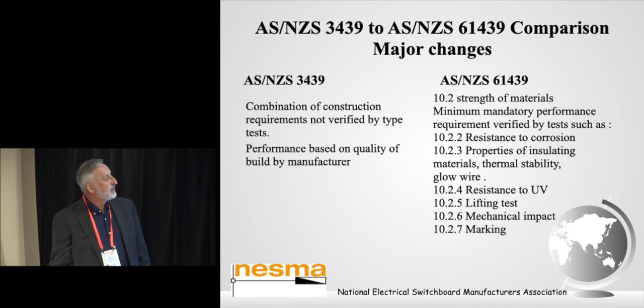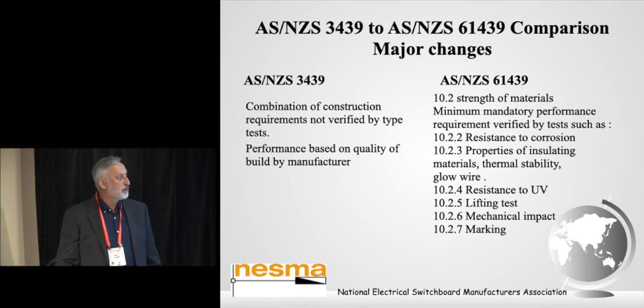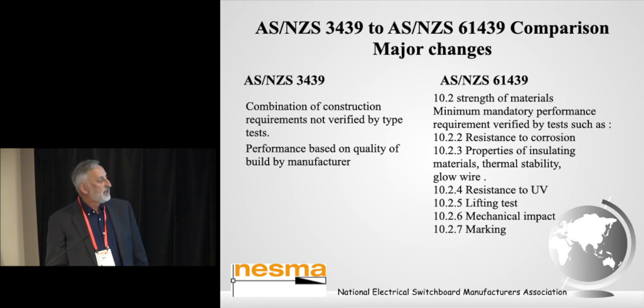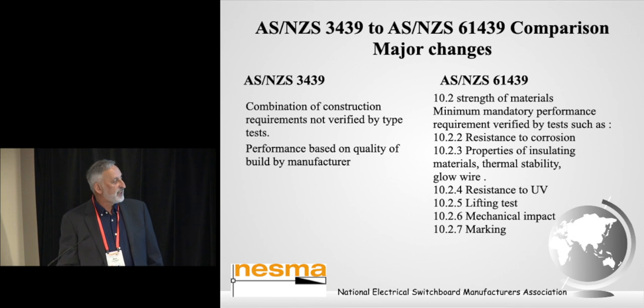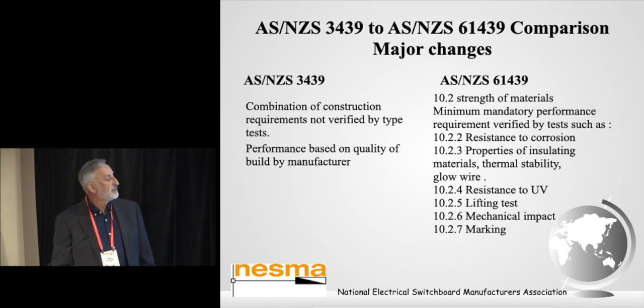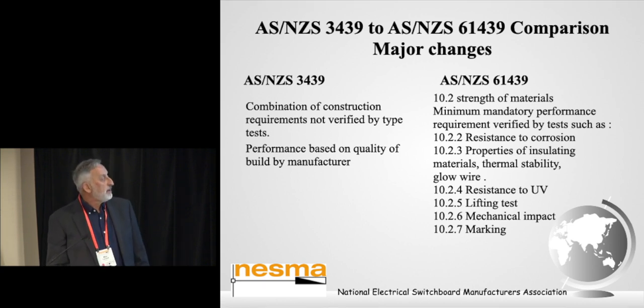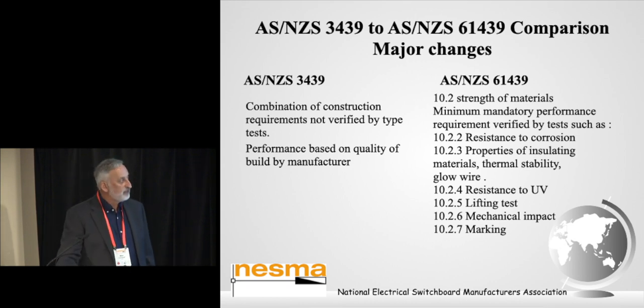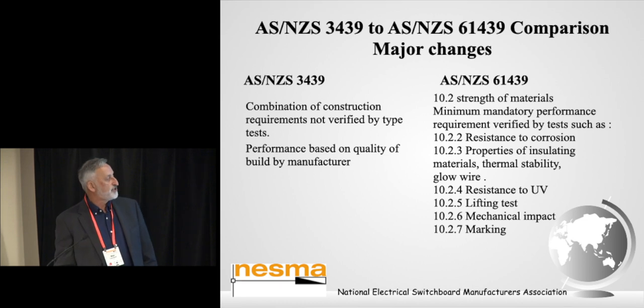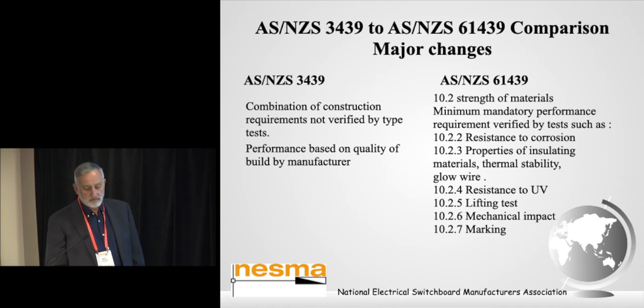So major changes that are really coming in are the clause under 61439 at 10.2. This clause is titled Strength of Materials, and you have minimum mandatory performance requirements which are to be verified by test. Resistance to corrosion, properties of the insulating material, so glow wire tests on busbar supports and plastics that are used. Resistance to UV for the external enclosure, a lifting test, mechanical impact if required, and marking. So those particular areas were loosely handled, I believe, by the combination of construction requirements, but they weren't verified by type tests. But that performance was based really on the quality of the build by the manufacturer.